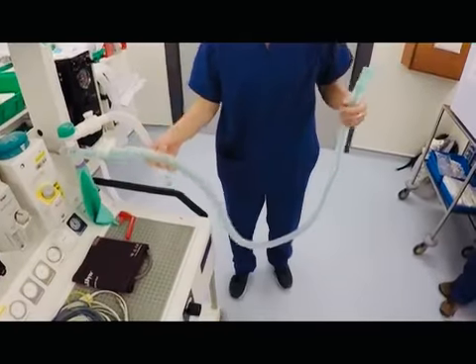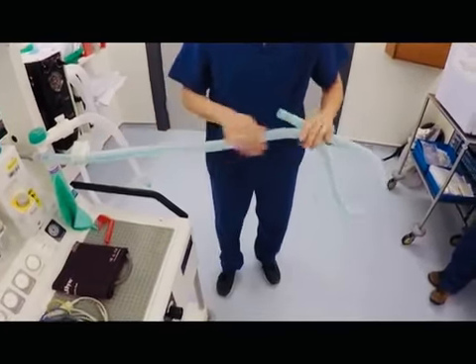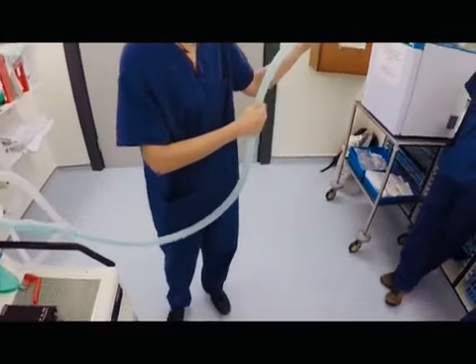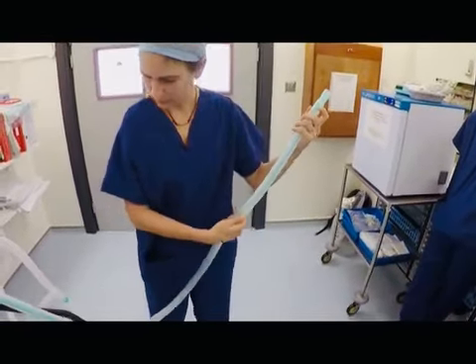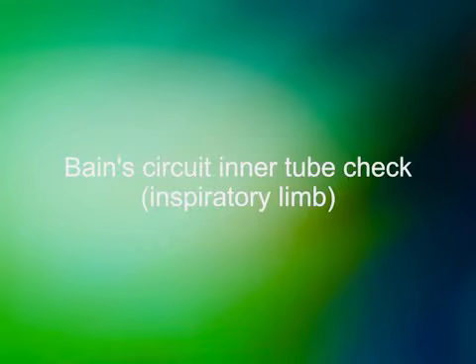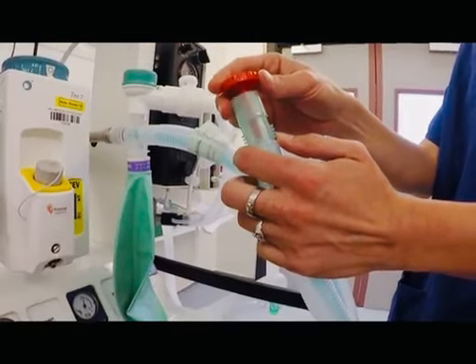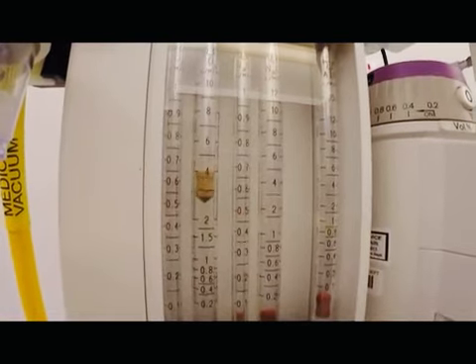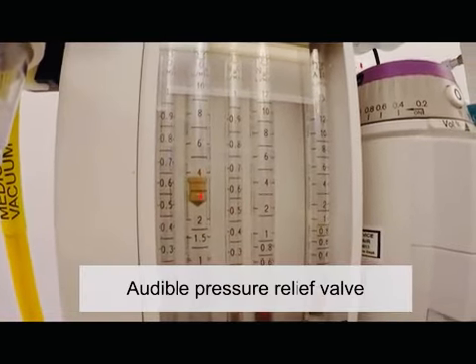The breathing circuit, in this instance a Bain circuit, now needs to be visually inspected, followed by checking the integrity of each limb of the circuit. The inner limb running from the common gas outlet to tip is checked by using an appropriate device, little finger or plunger of a 2 ml syringe, to occlude the inner outlet. This should cause a pressure build-up through the inner tube and the back bar, causing the bobbin of the flow meter to drop and the pressure valve on the back bar to release. The bag should not fill.